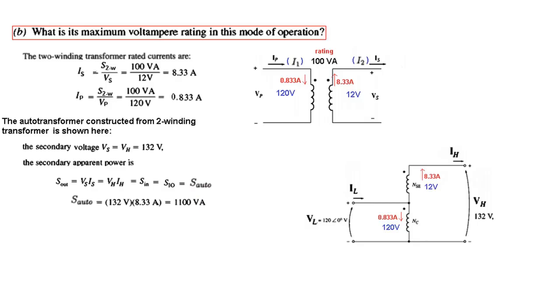So V secondary 132 volt, I secondary 8.33. So multiply this, we got the auto voltage or auto transformer power to be 1100 volt ampere. Note in the two winding it was 100 volt ampere but in this case it can handle up to 1100 volt ampere. This is the same transformer just when connected in auto mode the power handling capacity has increased.